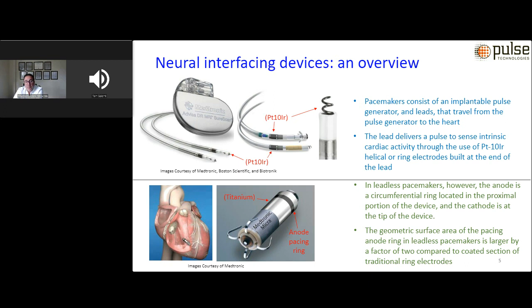But now that I've provided a brief overview of the various sorts of neural interfacing devices and the way they function, we can shift gears a little bit and talk about the materials used in the fabrication of electrodes and electrode arrays for these devices. Generally speaking, there are currently two materials commonly in practice. The first one is a platinum iridium alloy, which is the most commonly used alloy due to its unique chemical, electrochemical, and mechanical properties. It is used in the manufacturing of leads and electrodes in neurostimulation devices, cardiac devices, and also cochlear implants.